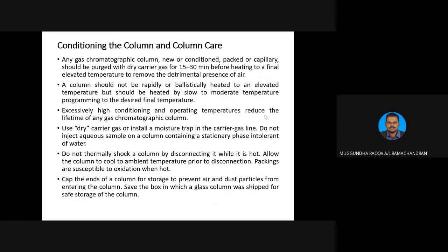Class, conditioning the column in column care is also a very important procedure that all of you have to know. Basically, for any chromatography column, new or conditioned, packed or capillary, before we run, we will usually purge with a dry gas for 15 to 30 minutes before heating to the final elevated temperature, basically to remove the presence of air.